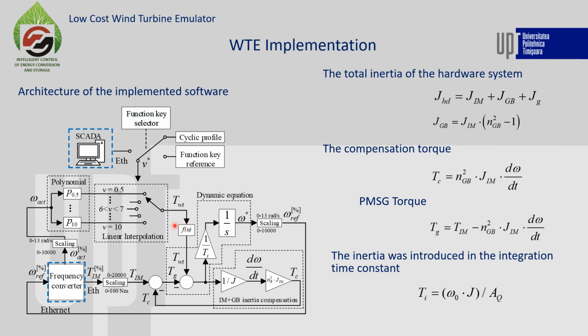So we have the wind turbine torque, we have the generator torque, and all that remains is to apply the dynamic equation of motion in order to obtain the reference speed for the frequency converters, with the observation that the inertia J was introduced in the integration time constant.